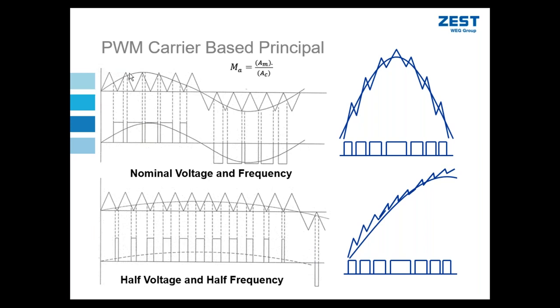I then create a carrier signal that represents my switching frequency. In this example, in one 50 hertz reference waveform, I have one, two, three, four, five, six, seven, eight, nine, 10, 11, 12. I've got 12 carrier frequency references. That means the switching frequency of this VSD is 12 times 50, because we're switching 12 times for every complete 50 hertz cycle. That gives me a switching frequency of 600 hertz.